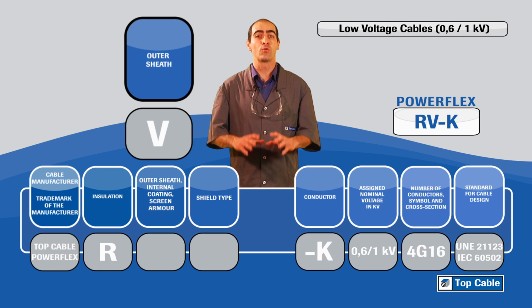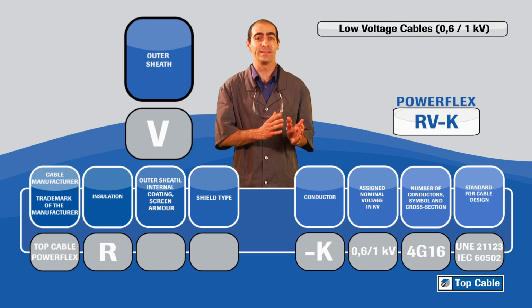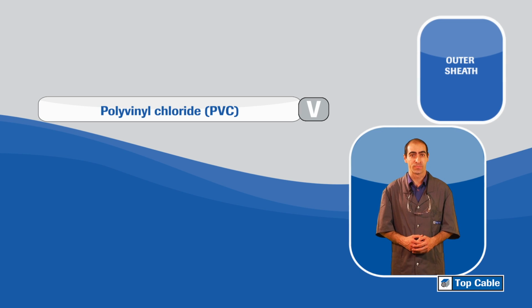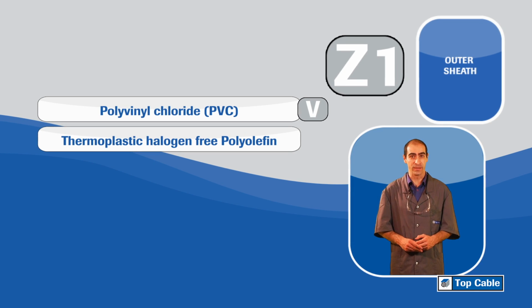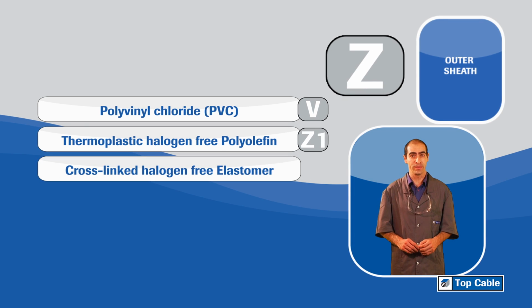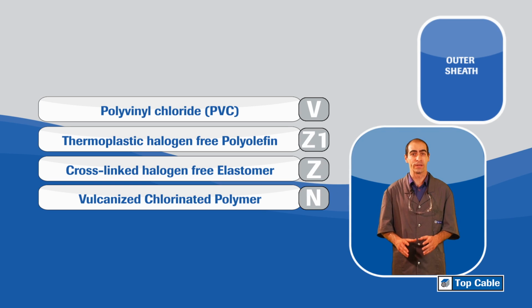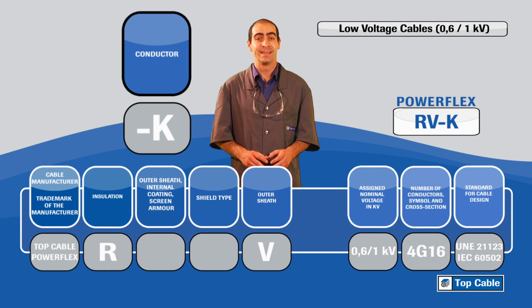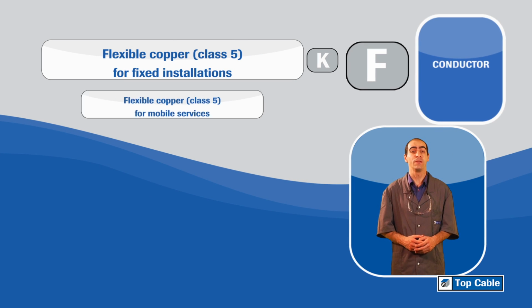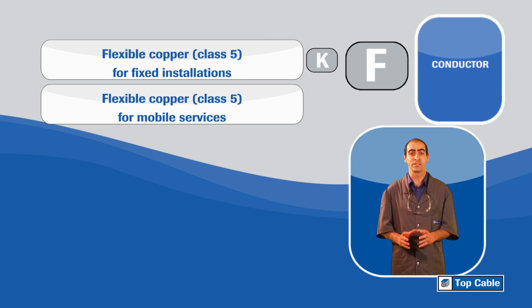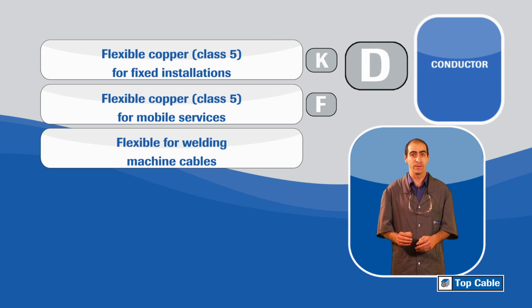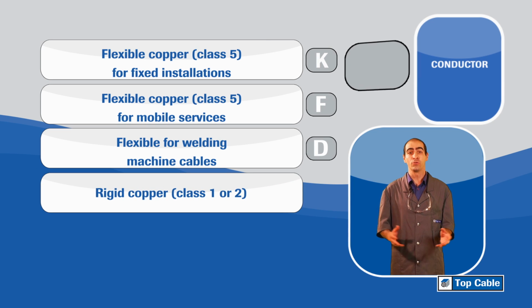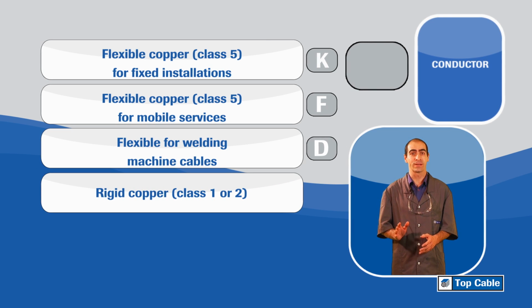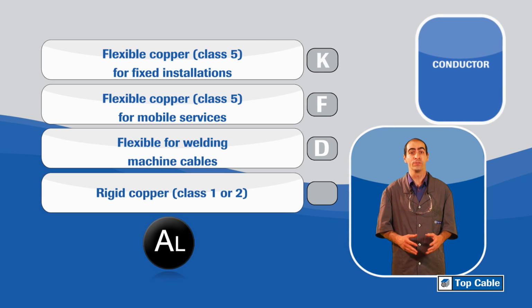PowerFlex's RV-K's outer sheath is made of PVC, as indicated by the letter V. Other possible outer sheaths are Z1, thermoplastic halogen-free polyolefin, Z, cross-linked halogen-free elastomer, N, vulcanized chlorinated polymer. The letter K means it is a flexible copper class 5 conductor for fixed installations. Other possible options are F, flexible copper class 5 for mobile services, D, flexible for welding machine cables. When there is no letter, the conductor is rigid copper, class 1 or 2. If the conductor is aluminium, AL is indicated.